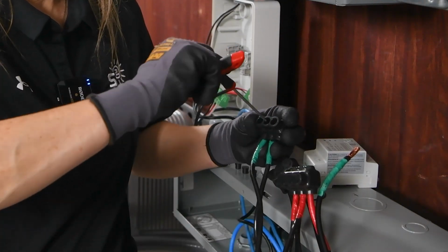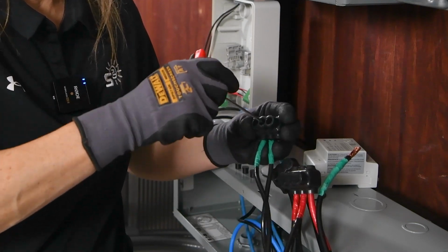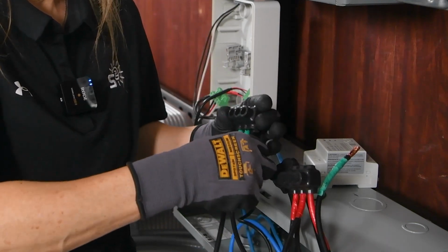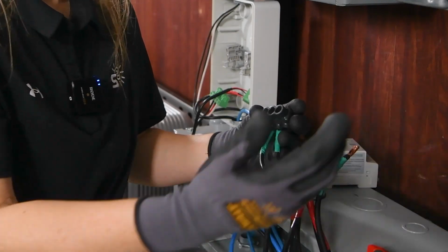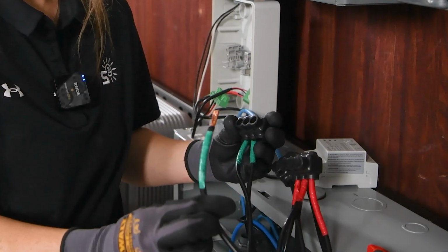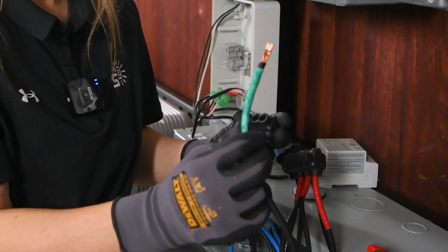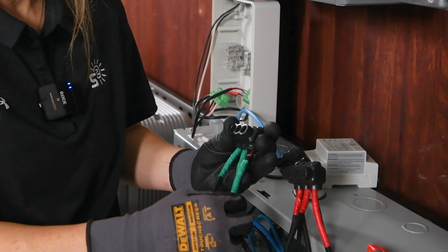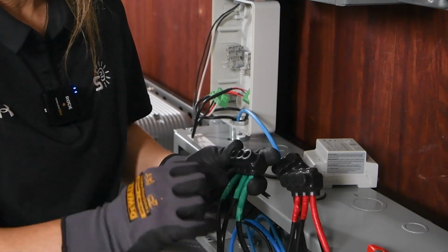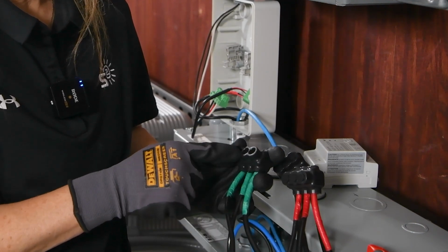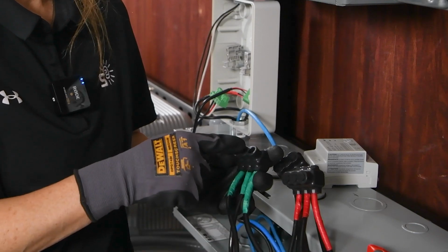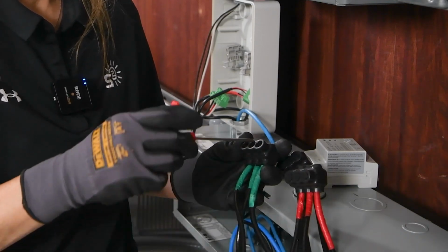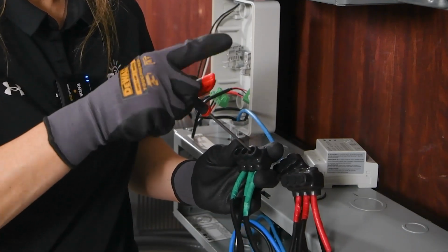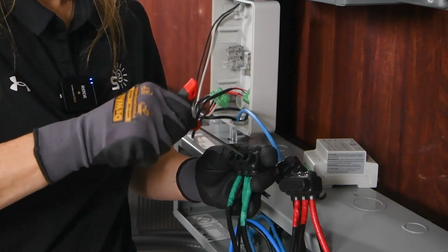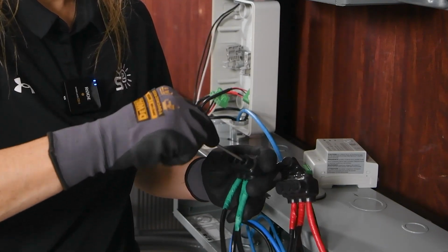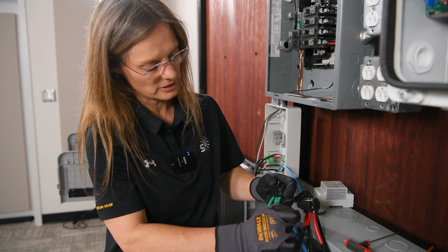And these are both 8-gauge wires coming from your batteries. Because they're being paralleled, your amperage will increase, and so for safety purposes, we will increase that wire gauge from an 8-gauge to a 6-gauge going into our inverter. So this wire that's going from our batteries to our inverter is our increased wire gauge, which will be our 6-gauge. So we'll tighten that down. Make sure these are good and snug. So those are all good and tight.